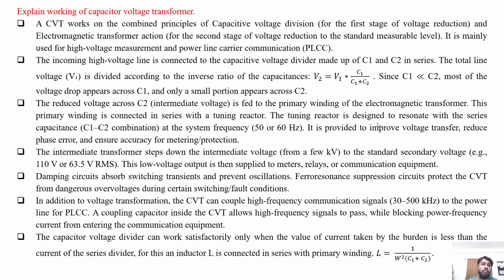The incoming high voltage line is connected to the capacitive voltage divider made up of two capacitors connected in series, that is C1 and C2. This C1 is a low value or high voltage capacitor and C2 is the low voltage capacitor. So the total line voltage V1 is divided according to the capacitor voltage division principle. So V2 is equal to V1 into C1 upon C1 plus C2, the combination.